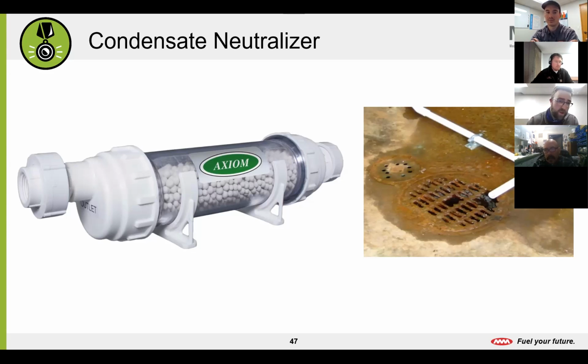So if you look at this picture here on the right, that is a metal floor drain that has had a rough go of it. So what happens here is that if left untreated, that condensate, that water coming off of these boilers, will start to eat away at the surfaces that they make contact with, which is definitely a no-go. We have to avoid that, and that's why maintenance on all boilers, but particularly on condensing boilers, is so important here. And the way we maintain this water is on the left here.